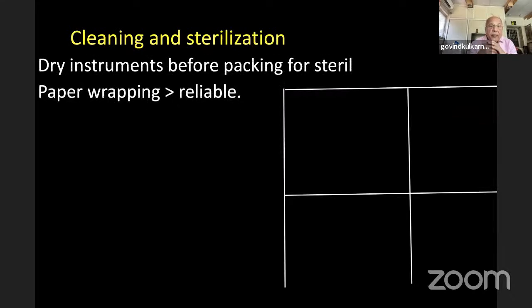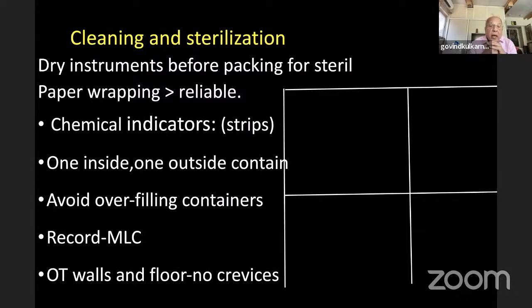Cleaning and sterilization. Dry the instruments before packing for sterilization. Paper wrapping is better and more reliable than cloth wrapping. Chemical indicators are important. Strips should be used, one inside and one outside the container. Avoid overfilling the containers because the steam will not enter an overfilled container. Records are important from the MLC point of view. OT walls and floor should have no crevices.